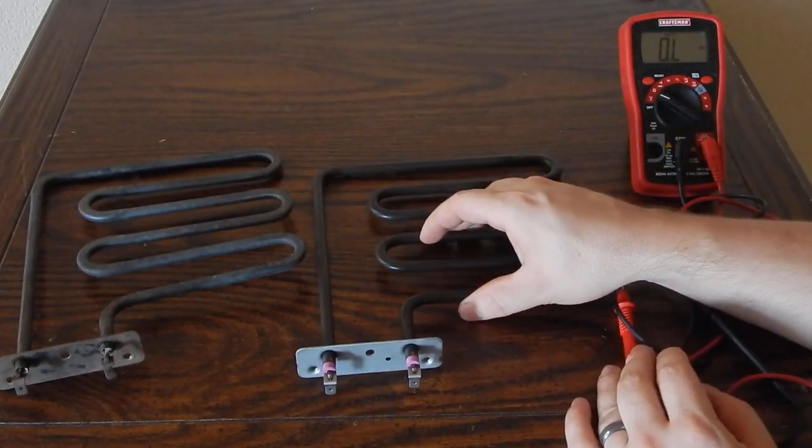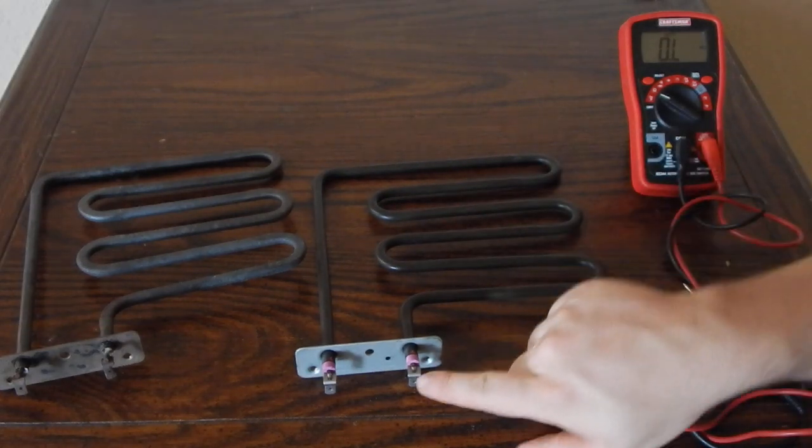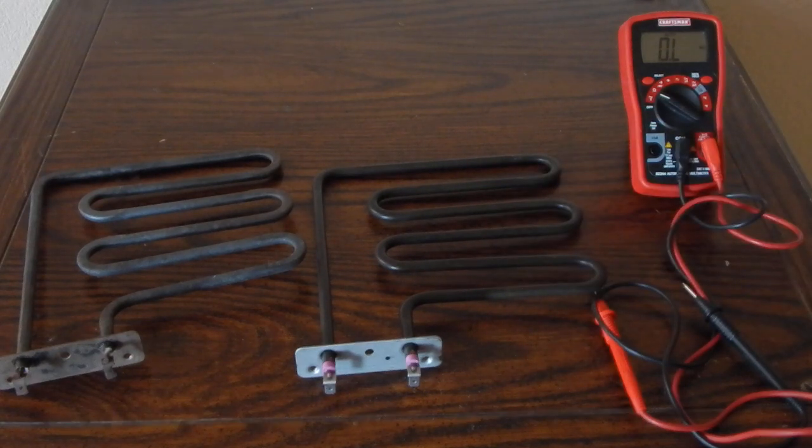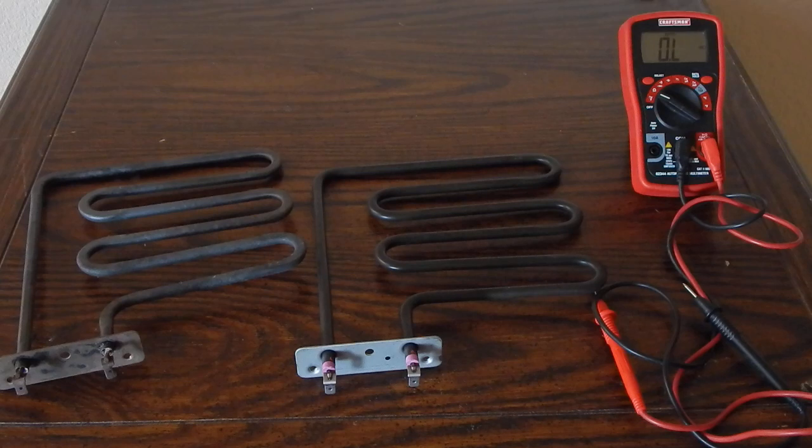And that's pretty much all there is to it. But you do need to check and make sure that there's no continuity between this lead here and the outside casing. If there is, then the coil is bad and you need to toss it and get a new one.